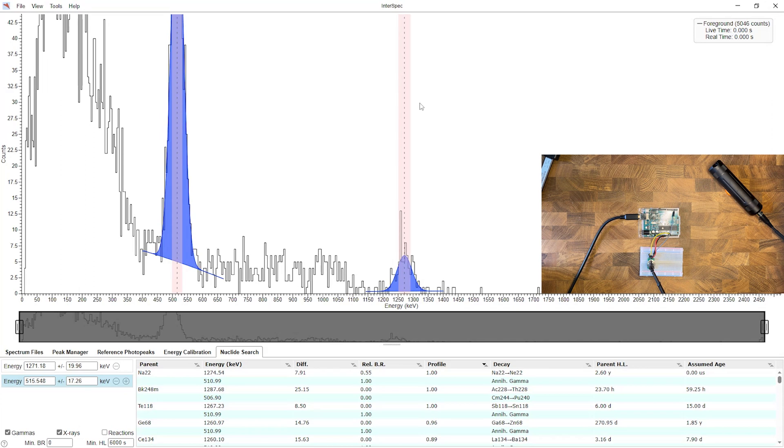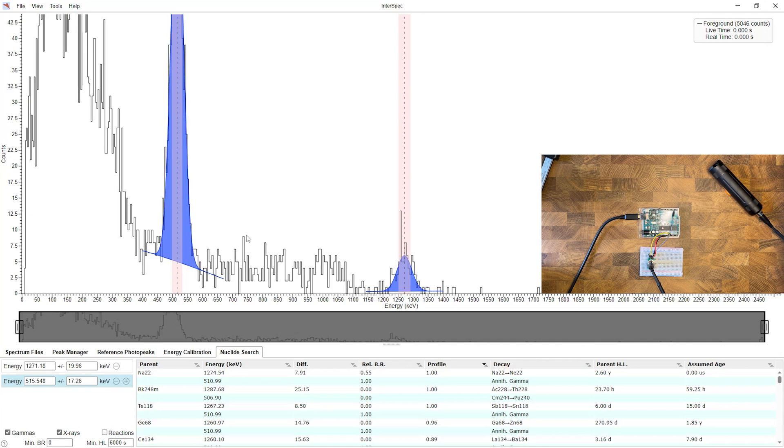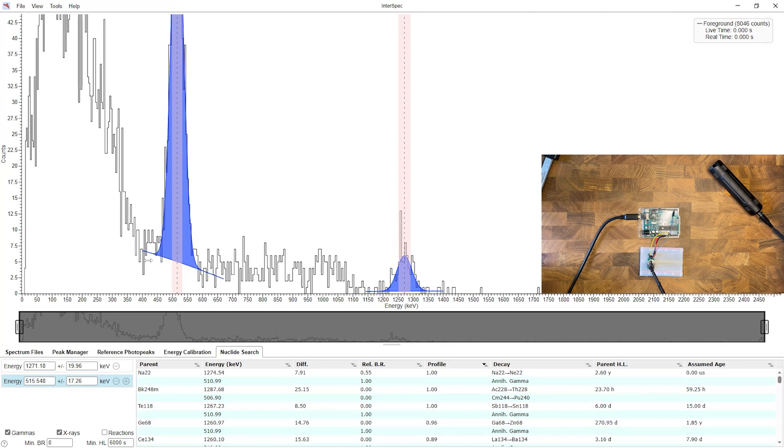So yeah that's how you do more advanced gamma spectroscopy with your RadView. To recap, you want to calibrate your detector with a known source that has many peaks. Radium is a good one. Europium also works if you're going to be doing this frequently. You want to export that calibration profile after you calibrate it. Then you can take any gamma spectrum, put it into a notepad file, open it up and then drop your calibration profile on top and then your channels will be in the correct energy levels.